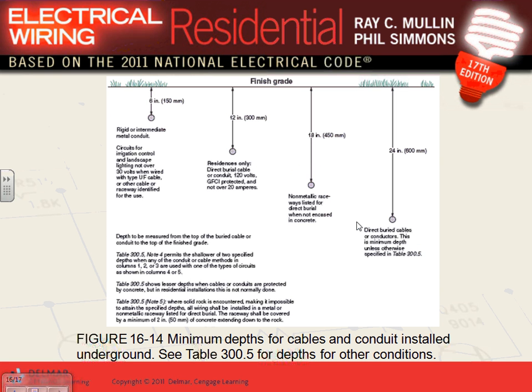If you use a PVC conduit, which is the most common conduit we use, like I told you guys, you pull conductors inside it, you can go 18 inches, no concrete, nothing, 18 inches. If you bury direct buried UF cable in other than GFCI protected, non-residential, you have to bury direct buried cable at 24 inches. Any question, guys, about these requirements? Very, very important. This table is extremely important. Any question about that?